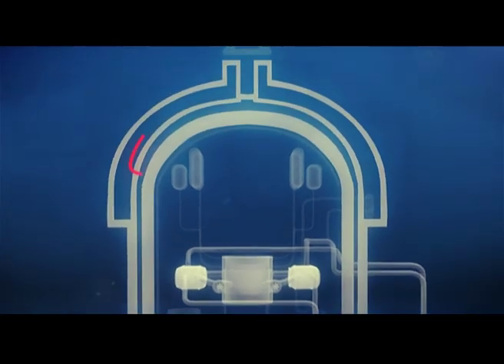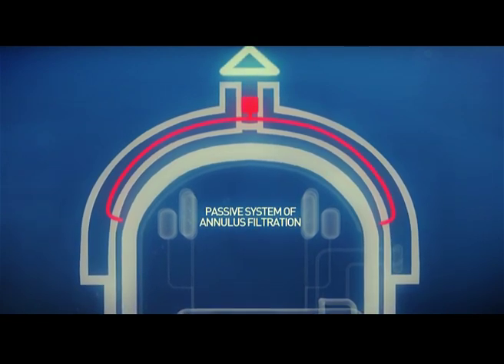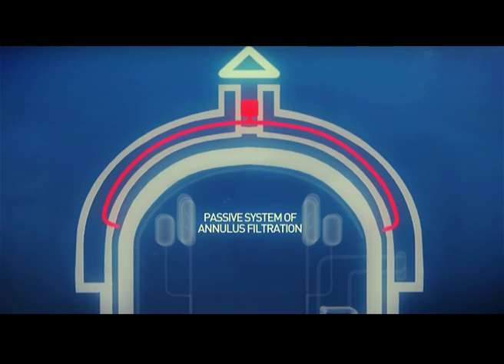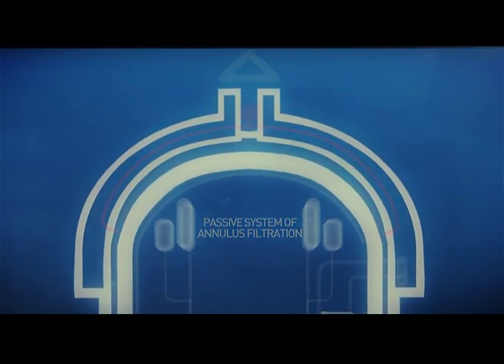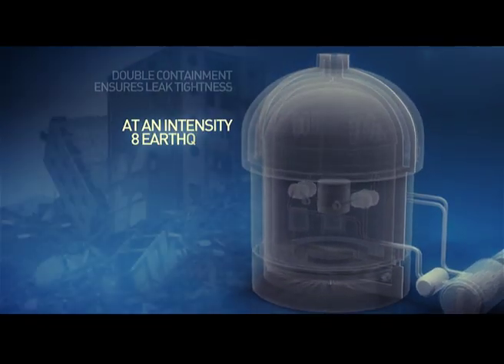There is an annulus between the inner and outer shielding. It is fitted with a system to filter gases incoming from the reactor hull. The reinforced double containment retains leak tightness at an intensity 8 earthquake and a crash of up to 200-ton aircraft.